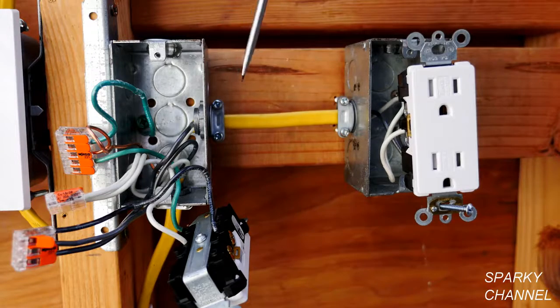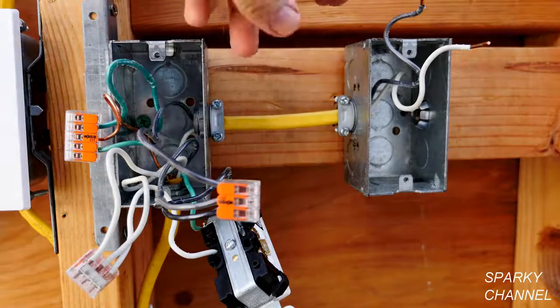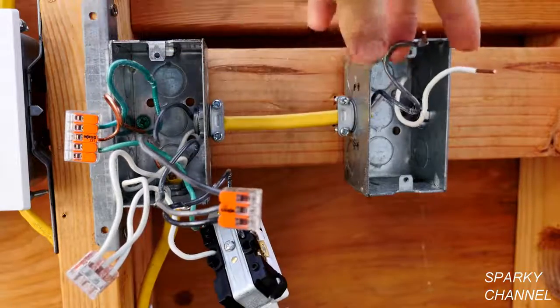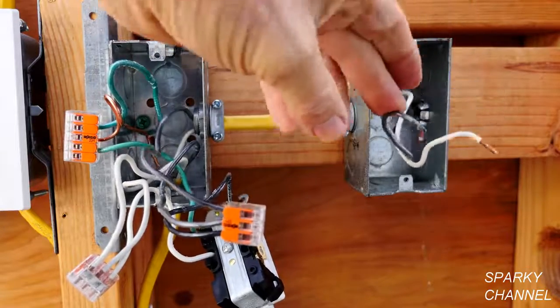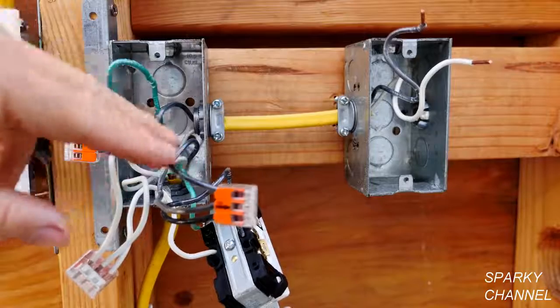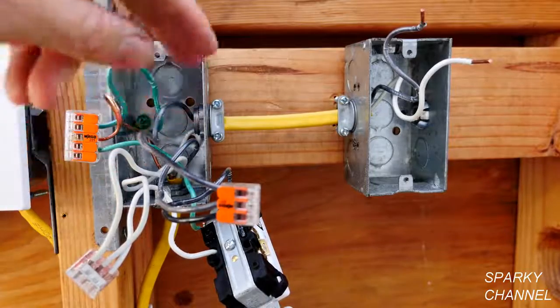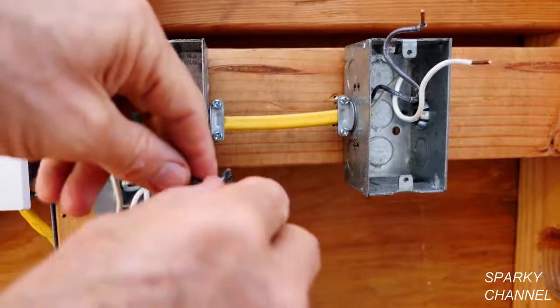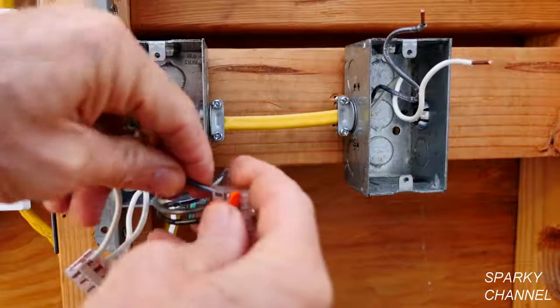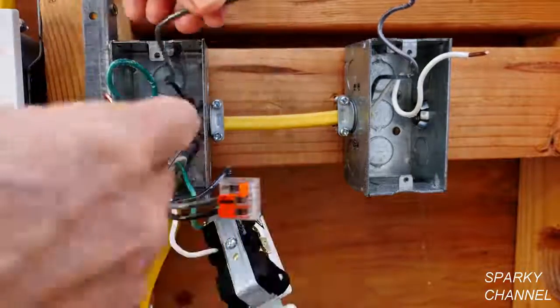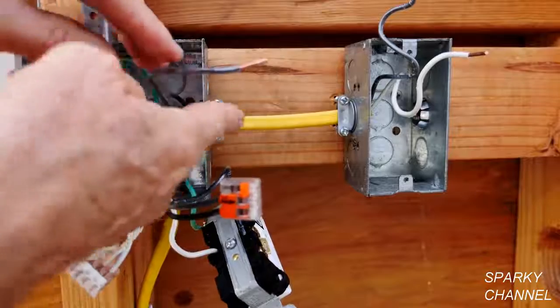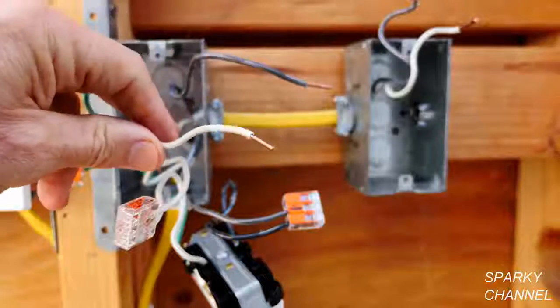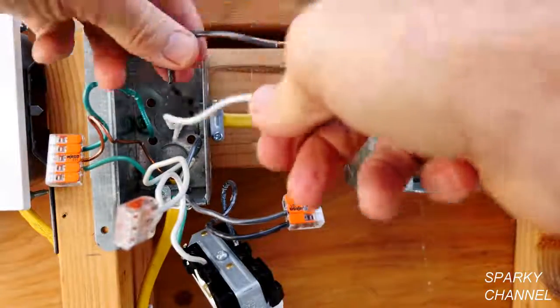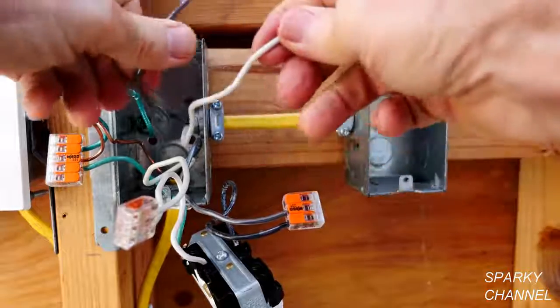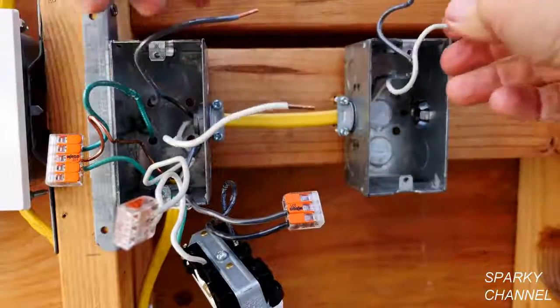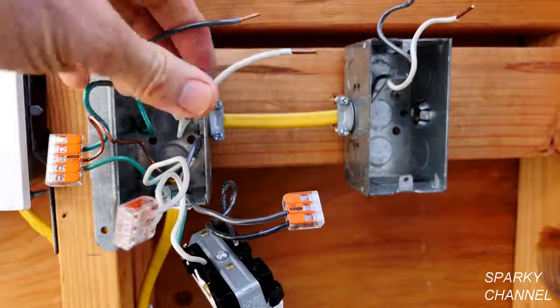And the way we're going to do that is test for continuity. I've removed this receptacle, and there's your white neutral and your black hot. Now on this box, I'm going to isolate the black hot and the white neutral. That goes to the next receptacle, and we're going to test it for continuity. So here's the black hot that goes to the next receptacle. Okay, here's the white neutral that goes to the next receptacle. So we've isolated these two wires and these two wires. We have to check for continuity.